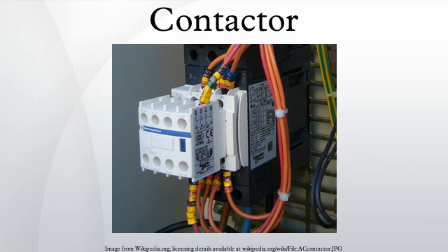The break arc is typically more energetic and thus more destructive. The heat developed by the resulting electrical arc is very high, ultimately causing the metal on the contact to migrate with the current. The extremely high temperature of the arc cracks the surrounding gas molecules, creating ozone, carbon monoxide, and other compounds. The arc energy slowly destroys the contact metal, causing some material to escape into the air as fine particulate matter. This activity causes the material in the contacts to degrade over time, ultimately resulting in device failure.